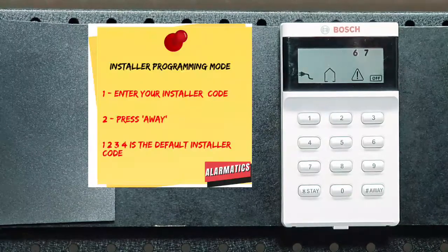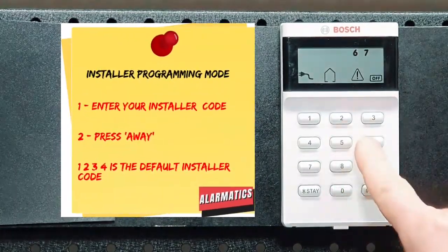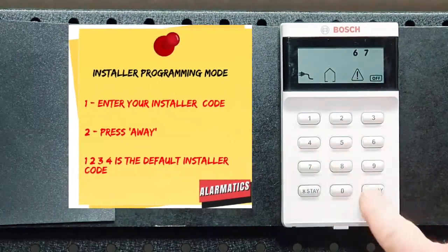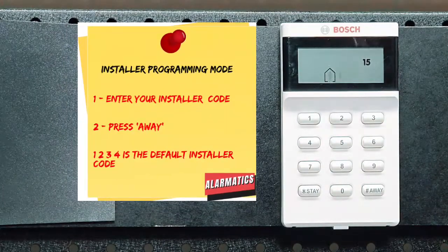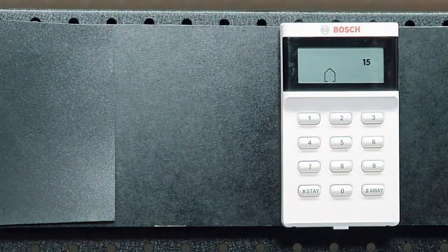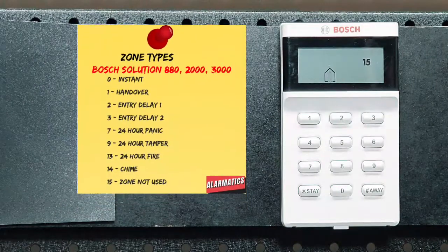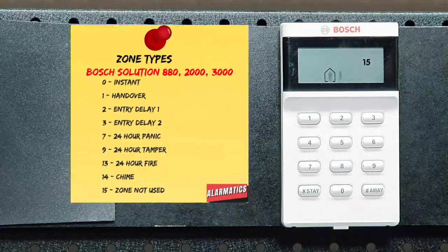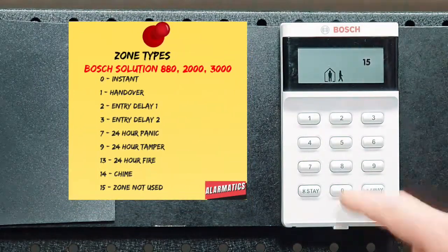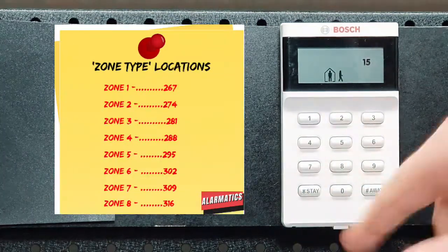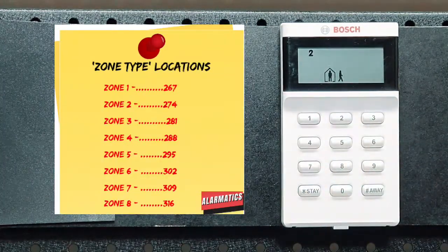Of course, we need to go into installer programming mode. I'll do that with my new installer code and press away. I'm now in installer program mode. The zone types are listed on the screen there. To change the zone type for zone 1, I need to jump to location 267. So 267 and away. Okay, it's currently set to a 2.